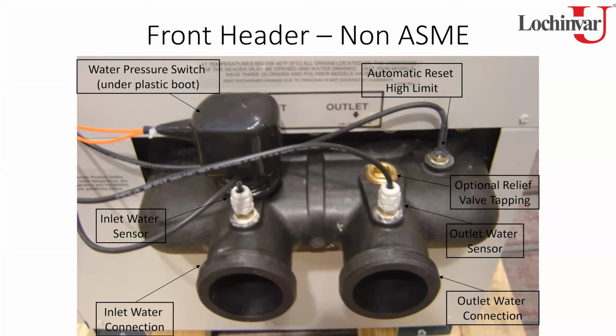If you're looking at delta Ts, and a lot of people like to get hung up on delta Ts, if you're just looking between what you would see at the inlet and outlet water connections, it'll be between a 10 to 14 degree delta T. Now, realistically, that's not a true delta T, because I'm not really looking at the inlet versus the outlet of the tubes. What I'm seeing is a blended temperature on the outlet side.